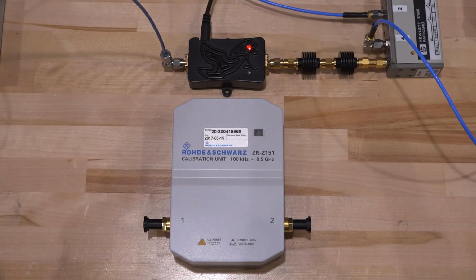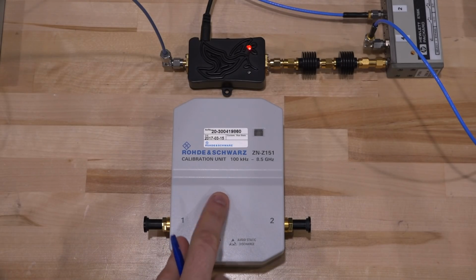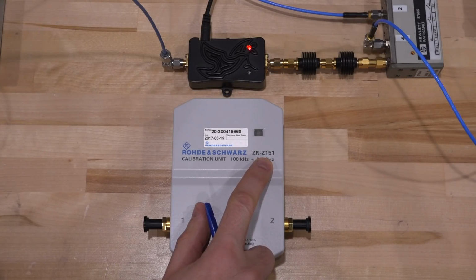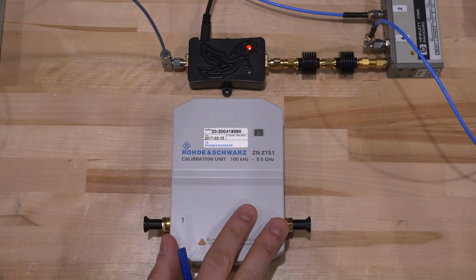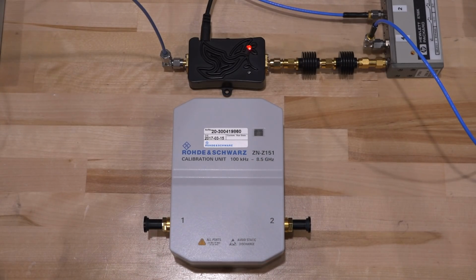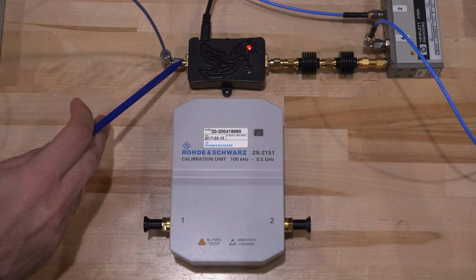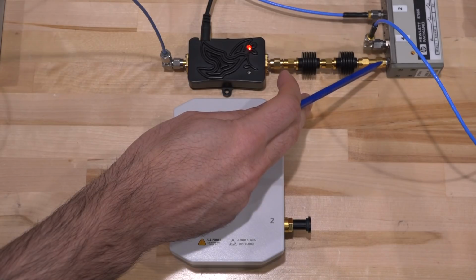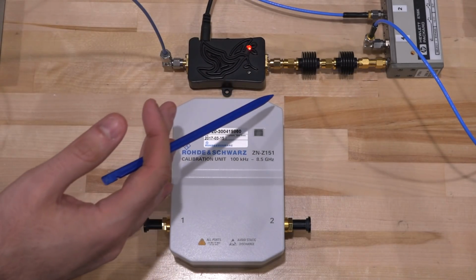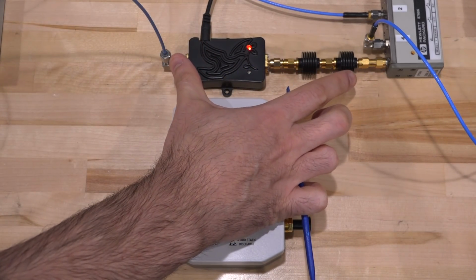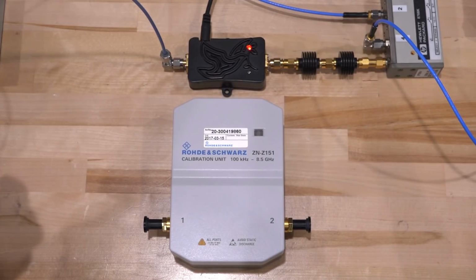Now, I've already shown you in the ZNL-E that you can use the built-in S parameter calibration wizard and use an eCal module like this one. This is a ZN-Z151, which is an 8.5 GHz calibration unit, and it will walk you through all of the calibration, and it's quite easy and straightforward to use. That's a nice feature that they have built into the software. Now what we're going to do is basically calibrate to this point and this point in the system, bringing the measurement planes, including all the cables and microwave switches, so we can measure the S parameter of this module by itself, including the attenuators.